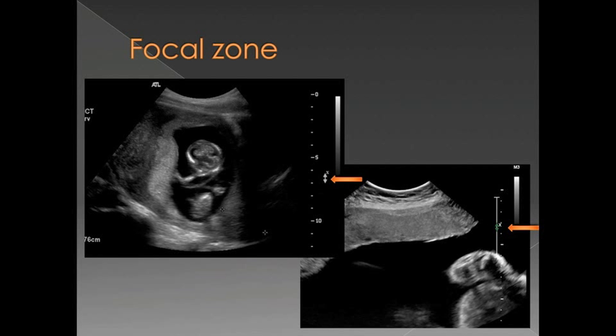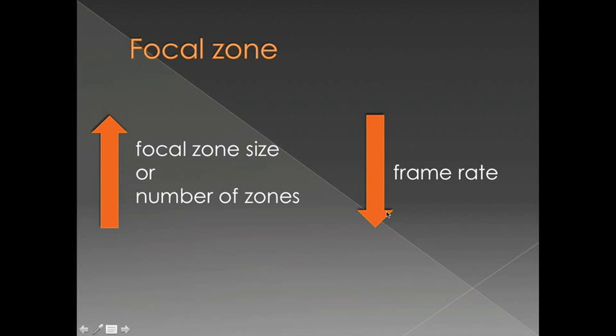As you increase the number of focal zones, the ultrasound machine is actually using multiple echoes focused at those different depths to create bands of the image that are then stitched together. So the wider the focal zone, the more echoes it takes to produce the image, and therefore, the lower the frame rate. So if you have a large number of focal zones, or if you have a large focal zone size, you're going to have a slower frame rate.